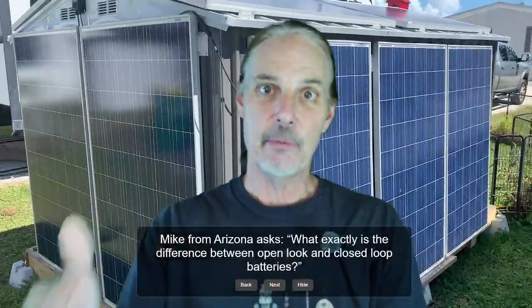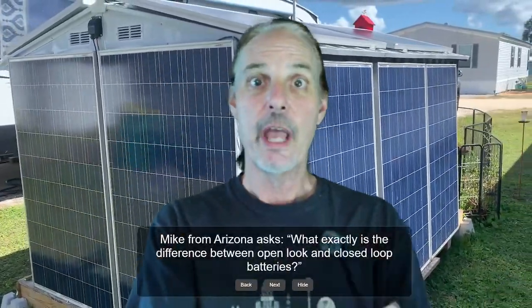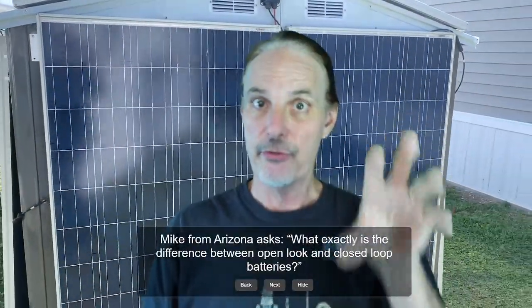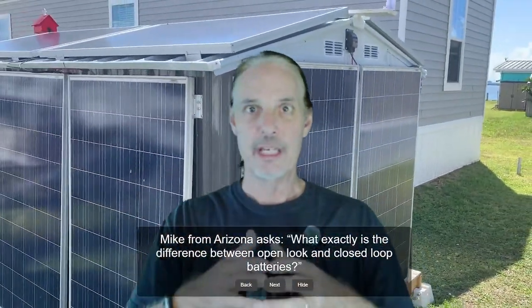Now, you can do a hybrid also, where I could have just left the three batteries connected and ran them closed loop with the inverter, and then left the fourth battery just open loop. There's no problem doing that either, except that the inverter is going to take its charging limits from the three batteries that are connected. Now, if you have enough batteries in that bank for it to exceed the charging capacity anyway, then that's really not too much of an issue.